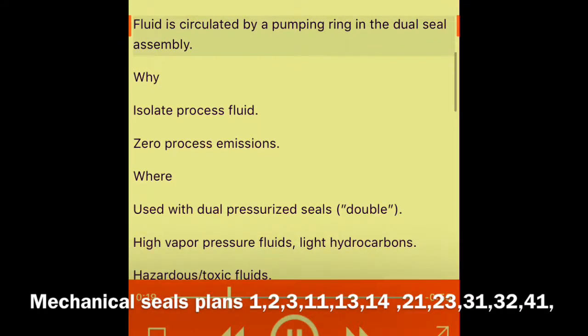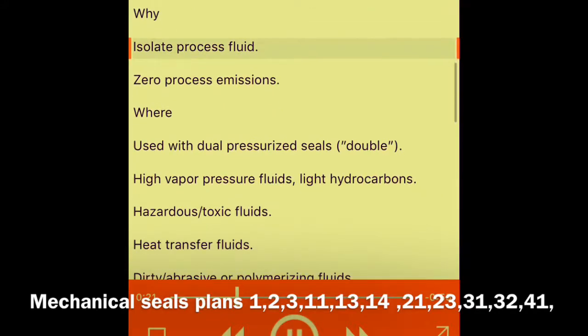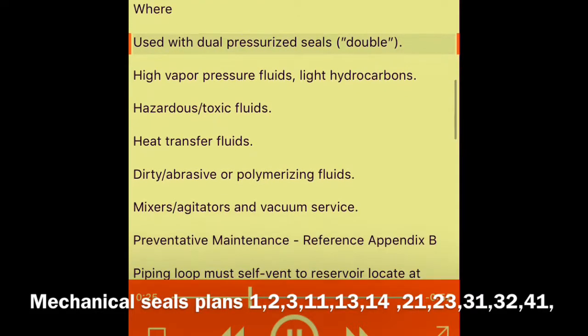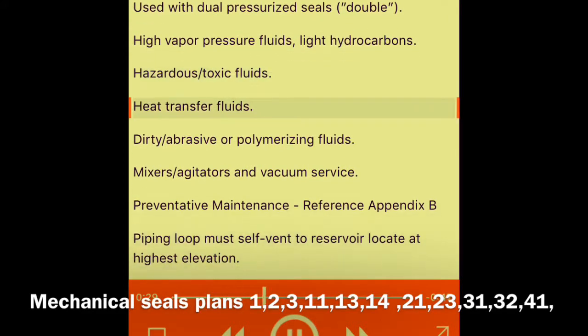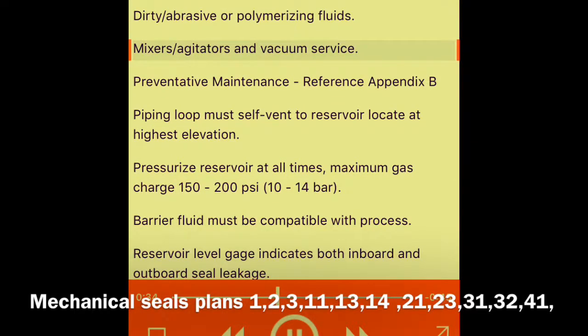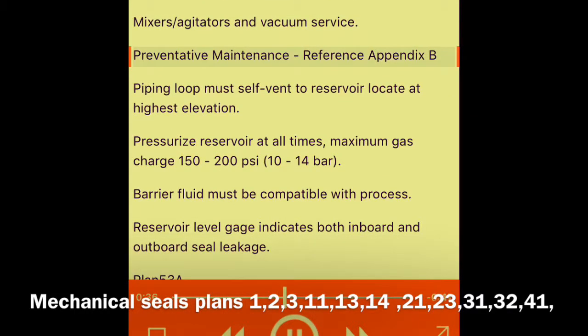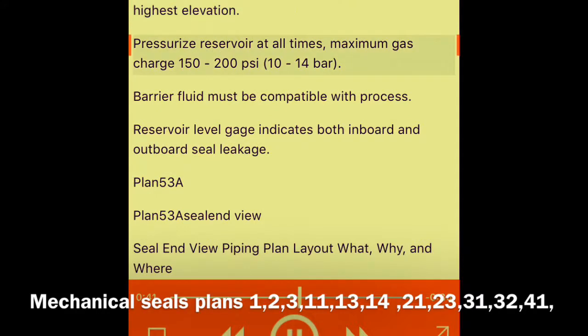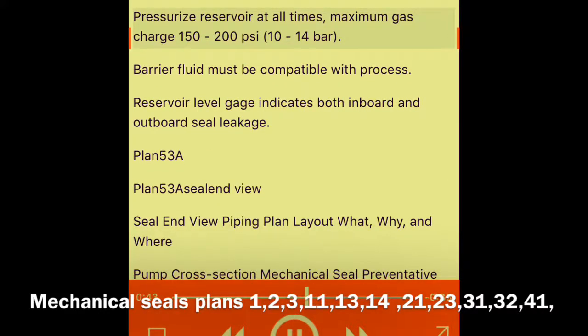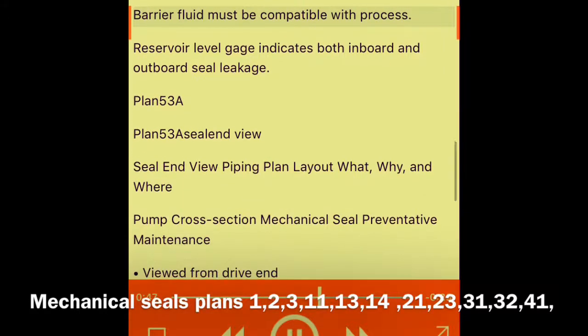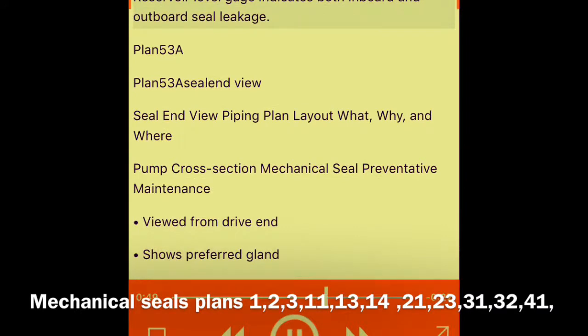Plan 53A: pressurized barrier fluid circulation through reservoir. Fluid is circulated by a pumping ring in the dual seal assembly. Why — zero process emissions. Where — used with dual pressurized seals for high vapor pressure fluids, light hydrocarbons, hazardous or toxic fluids, heat transfer fluids, dirty abrasive or polymerizing fluids, mixers, agitators, and vacuum service. Preventative maintenance: piping loop must self-vent to reservoir located at highest elevation; pressurized reservoir at all times; maximum gas charge 150–200 psi (10–14 bar); barrier fluid must be compatible with process. Reservoir level gauge indicates both inboard and outboard seal leakage.